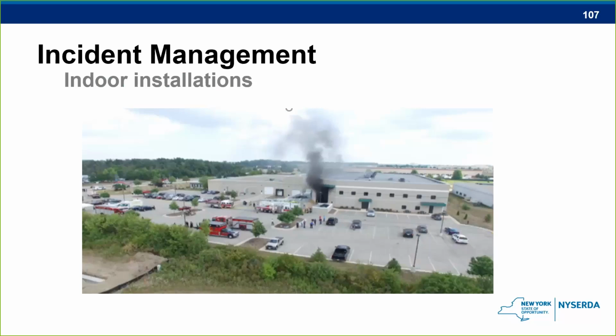So if you don't have the right proper density of water going in there to manage the fire, you're not doing a favor to the firefighters. Now they have to go in there and put more water on it with their hose lines. And if they are operating on it, we don't want them to go deep inside that room because of the fact that that stranded energy will still be there. Next slide.